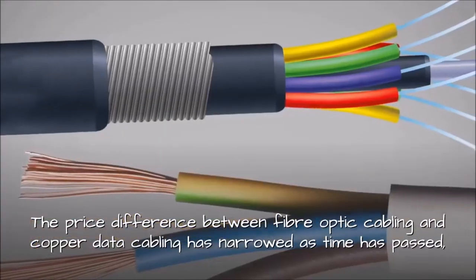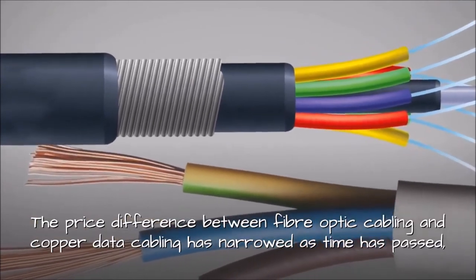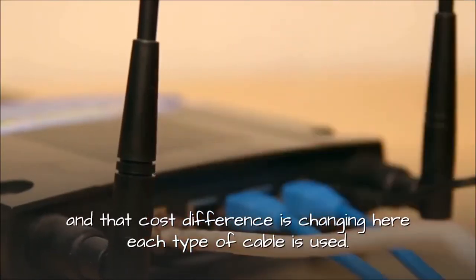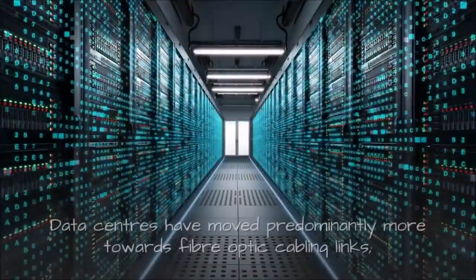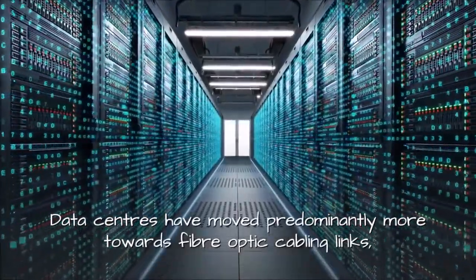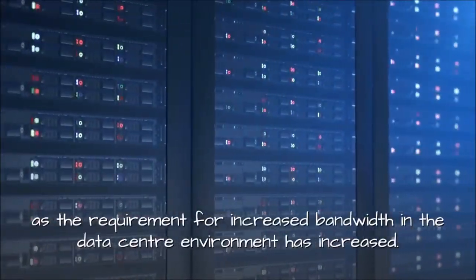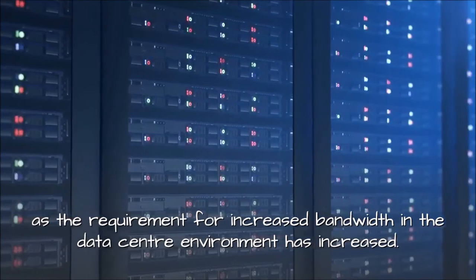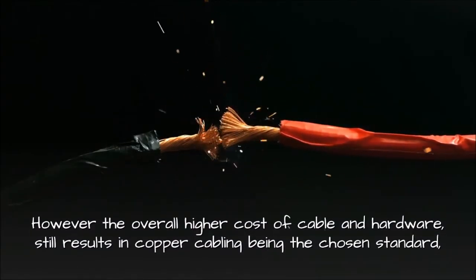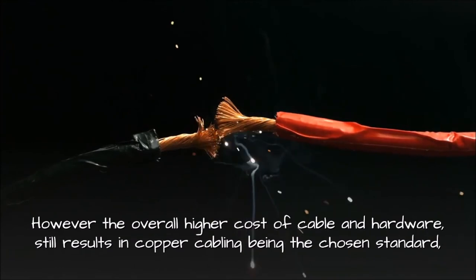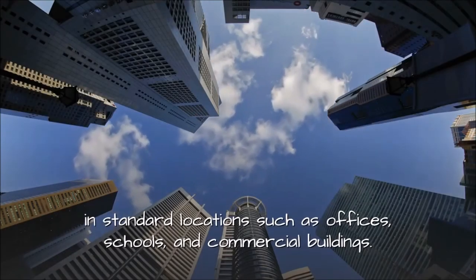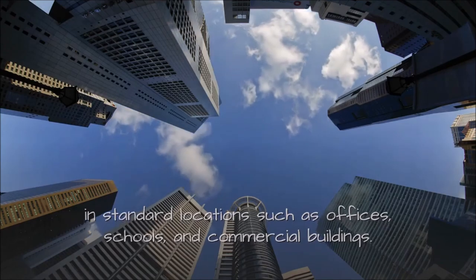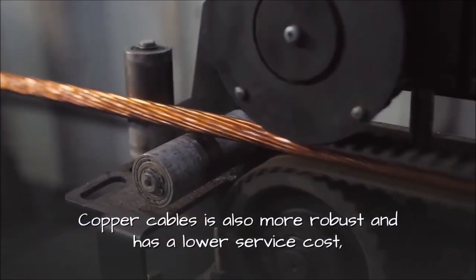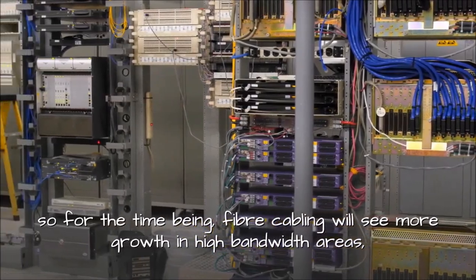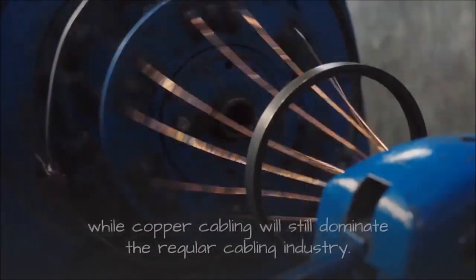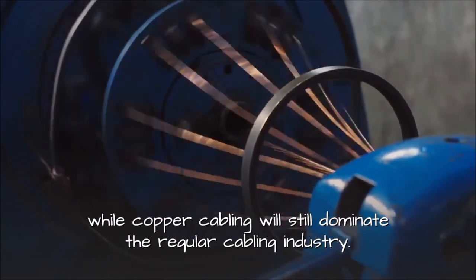Will fiber optics replace copper in the future? The price difference between fiber optic cabling and copper data cabling has narrowed as time has passed, and that cost difference is changing where each type of cable is used. Data centers have moved predominantly towards fiber optic cabling links, as the requirement for increased bandwidth in the data center environment has increased. However, the overall higher cost of cable and hardware still results in copper cabling being the chosen standard in standard locations such as offices, schools, and commercial buildings. Copper cable is also more robust and has a lower service cost, so for the time being, fiber cabling will see more growth in high bandwidth areas, while copper cabling will still dominate the regular cabling industry.